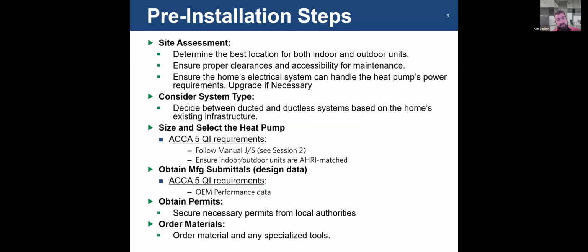So getting into installation, pre-installation setups: you've done your site assessment, you figured out where you're putting your indoor unit, you figured out where you're putting your outdoor unit. You verified that you've got enough electrical capacity. You've decided on the type of system you're using, whether it's ducted or ductless or whatever it might be. You've done your size selection. You've selected the type of heat pump you're putting in, or system for that matter. Doesn't necessarily have to be a heat pump. You've done your manual J. You've ensured that your indoor and outdoor units match, and you have an AHRI rating on it. You've got your manufacturer submittals, so you know all your sizes, capacities, and such. You've obtained your permits, you've ordered your materials, and now you're going to do your installation.